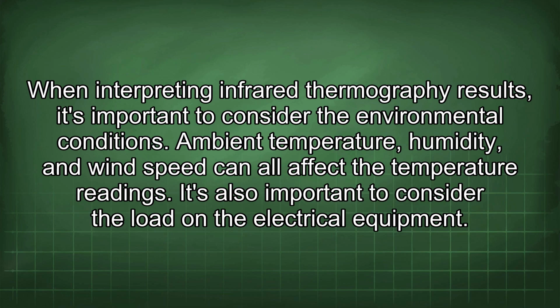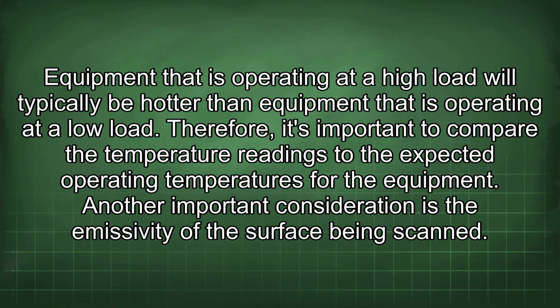When interpreting infrared thermography results, it's important to consider the environmental conditions. Ambient temperature, humidity, and wind speed can all affect the temperature readings. It's also important to consider the load on the electrical equipment. Equipment that is operating at a high load will typically be hotter than equipment that is operating at a low load. Therefore, it's important to compare the temperature readings to the expected operating temperatures for the equipment.